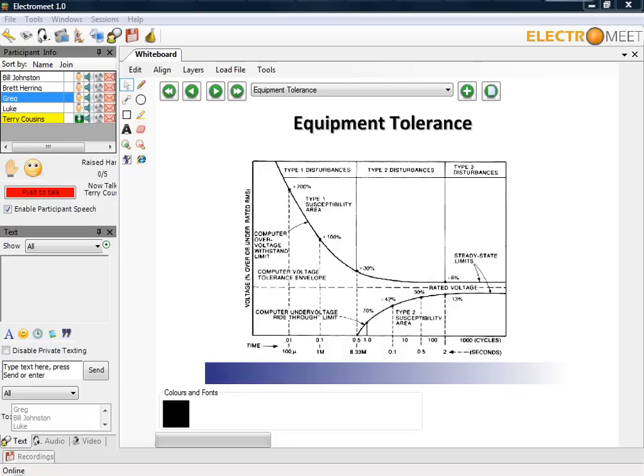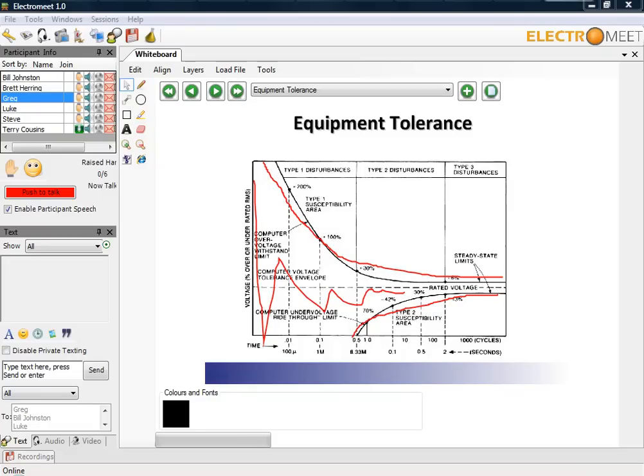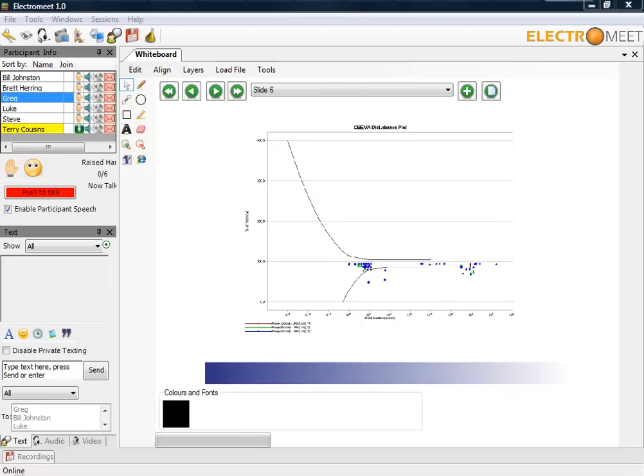All equipment has a tolerance to power disturbances, and the Computer Business Equipment Association in the U.S. has come up with a cone-shaped graph showing susceptibility to power interruptions. Anything that stays within this area would be okay; anything outside of this area would typically have a problem. Looking at real-world recordings, you can see disturbances plotted against this envelope — equipment outside this cone would possibly trip out, and we'd see those financial losses.